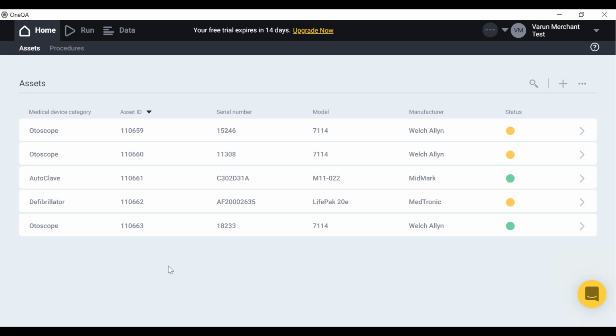So we have a set of customers we work with today who are using OneQA to test their devices. We go observe, virtually and even in person, their test times. They used to do it manually: take the procedures from the manual, set it up on the instrument, run the test, handwrite or type in Excel the results, and then port them over to the CMMS. We have them go through that cycle, and then do the same thing using OneQA. We have data points we've collected that measure the delta in minutes, and we use their typical technician per hour salary and calculate an estimate.